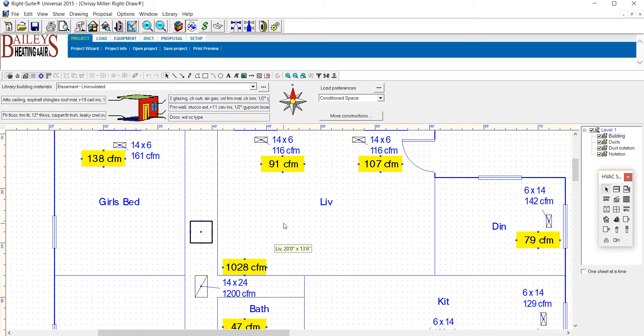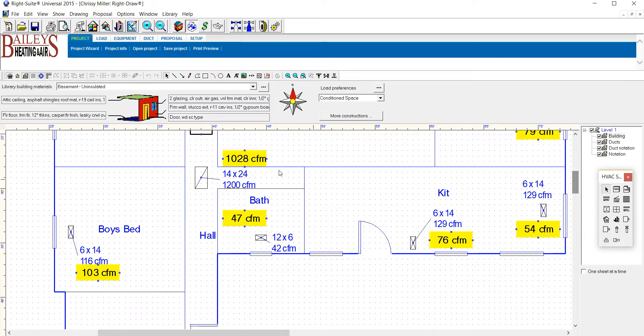The ductwork needs to be sealed. We could take care of that too when we move the furnace and we do a lot of sealing. You should have probably a second return or make this one bigger, make it a 20 by 30 instead of a 14 by 24.